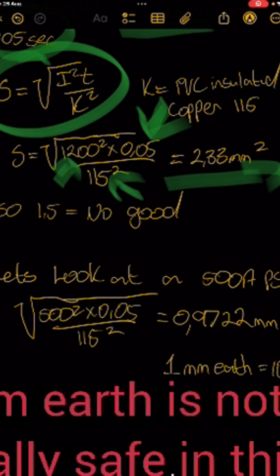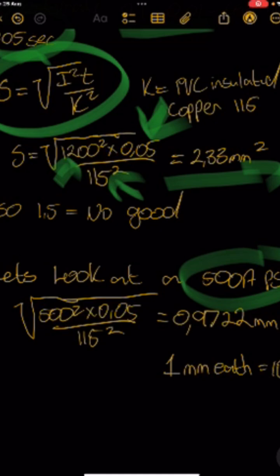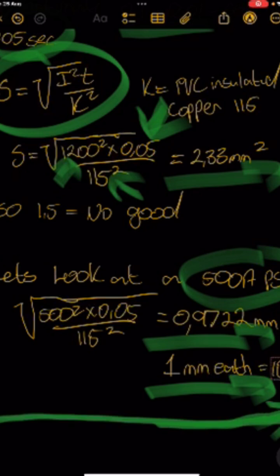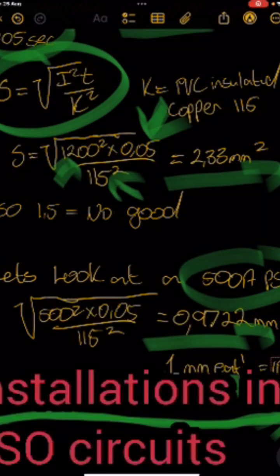It's basically exceeding its thermal limits. With a recalculation at a PSC of 500 amps, we come to the conclusion that we could use a one millimeter squared earth. Sometimes the 1.5 millimeter would be enough, but other times it will technically not be enough. It's more like a guess than really an engineering calculation.